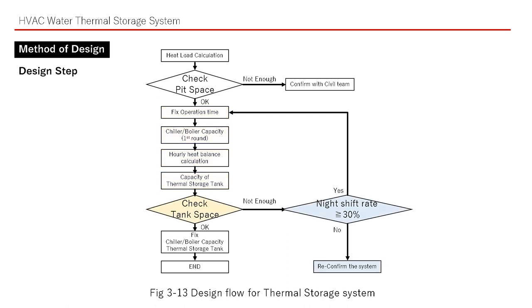Check tank space, and then check the night shift ratio. The thermal storage system is a method to reduce daytime peak load by using reasonable electric power at night. Therefore, we decide to adopt the thermal storage system when 30% or more of the load can be shifted to night time.